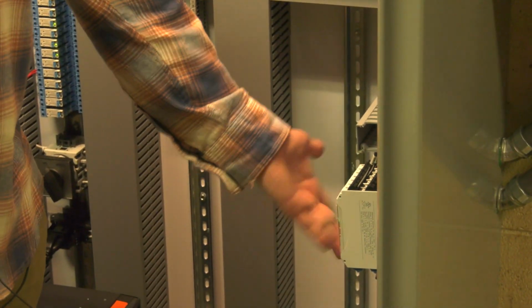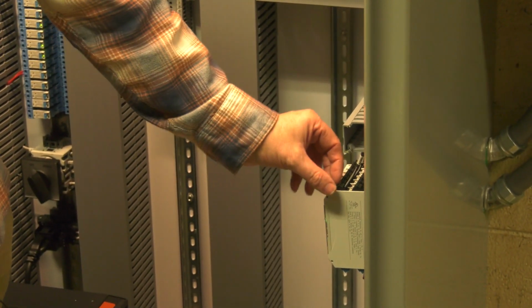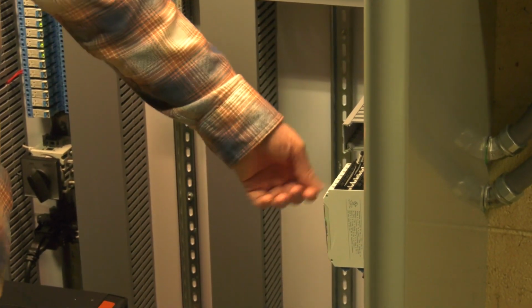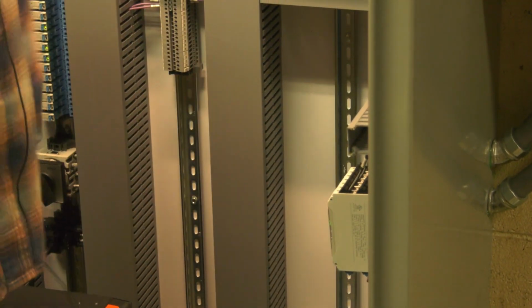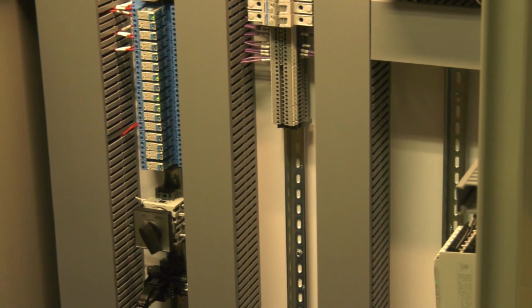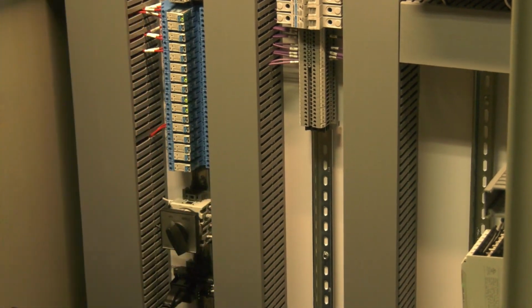This is intrinsic safety barriers. If they need to be replaced, just pop the terminals off, replace it and pop them back in. There's no dip switches, no configuration required. And that's pretty much it for this site.